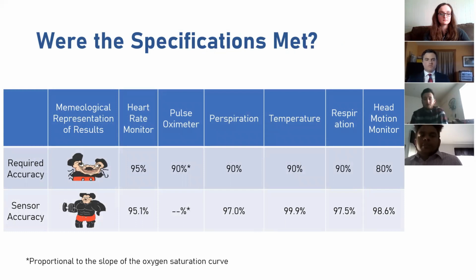So for the specifications, the ones that we presented earlier, we compared the precision of each sensor to the gold standard that was mentioned, and then evaluated the difference between the initial accuracy and the final sensor accuracy. Our final accuracies for each sensor are actually much higher than we initially thought, which is a good thing. We originally believed that the accuracy targets for the sensors should be scaled based on the relative importance of the sensor in the suite. So obviously the heart rate monitor is kind of like the central sensor, so that one was a lot higher. But it actually turns out that this was unnecessary, as all of the sensors ended up having an accuracy of above 95%. So that's an encouraging result, and it's definitely helpful for the final headset sensor suite product marketing, and we definitely achieved our goals in that regard.